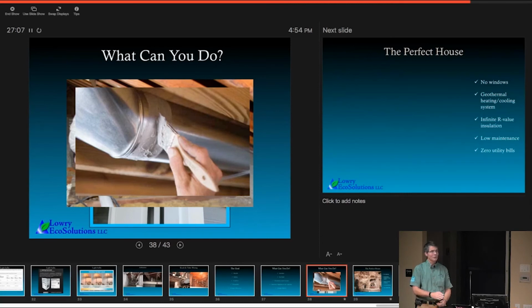Also, don't use duct tape, because duct tape is the one thing you can't use on ducts. Okay. Well, that's what I was going to use. But you can get aluminum tape, which is actually made for ducts. It's a little more expensive, but it does a great job. I think it's sometimes called UL 181 tape. But yeah, duct tape is not made for ducts. It's great for other stuff. But the mastic works well. You can use caulking, mastic, or that aluminum tape. If you can get to it, tape it up, seal it up.